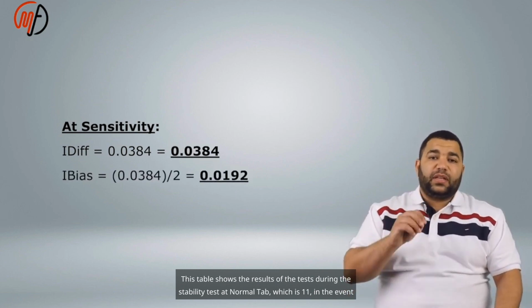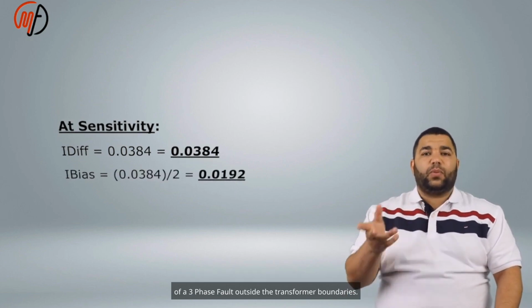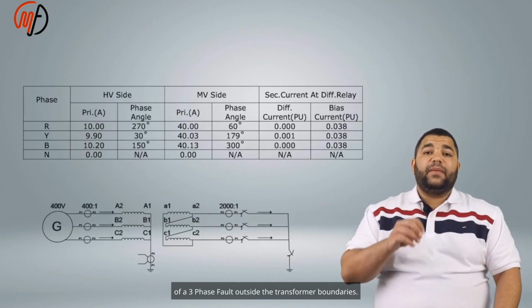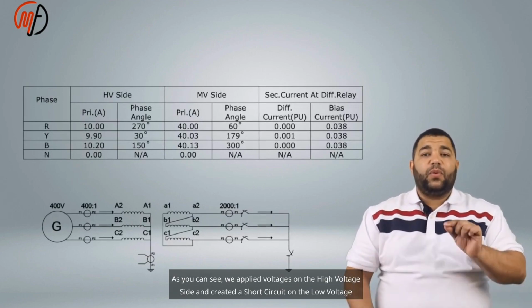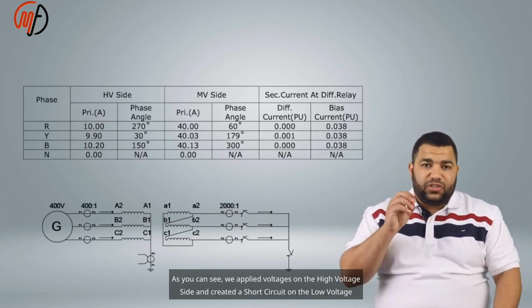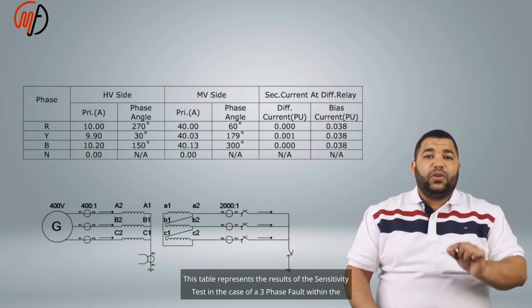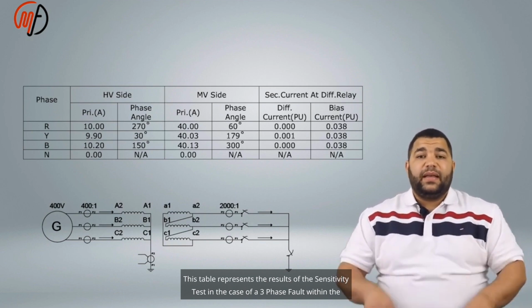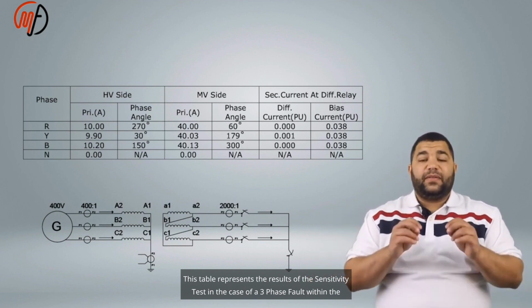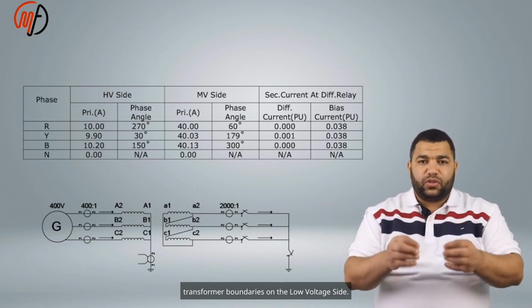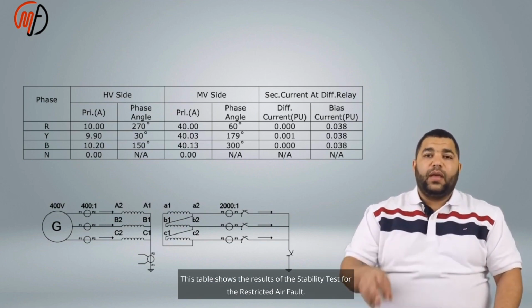This table shows the results of the test during the stability test at normal tap, which is 11, in the event of a three-phase fault outside the transformer boundaries. As you can see, we applied voltages on the high voltage side and created a short circuit on the low voltage side. This table represents the results of the sensitivity test in the case of a three-phase fault within the transformer boundaries on the low voltage side.